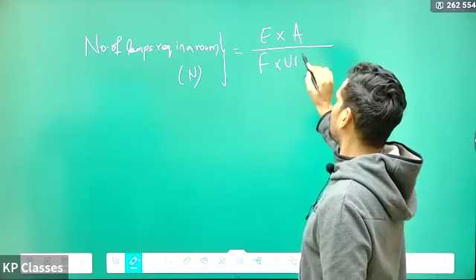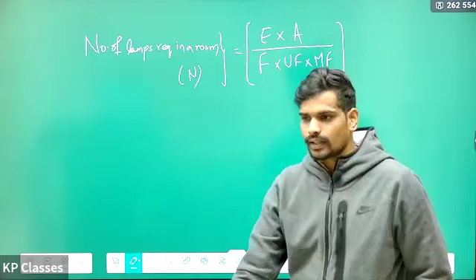The last concept before I end this particular topic of lighting is to understand the calculation of the number of lamps required in a room. Remember, number of lamps required in a room. How many lamps do you require in a room? There's a formula for that. That is illuminance required in the room multiplied by the surface area of the room divided by flux output of one lamp into utilization factor and maintenance factor.